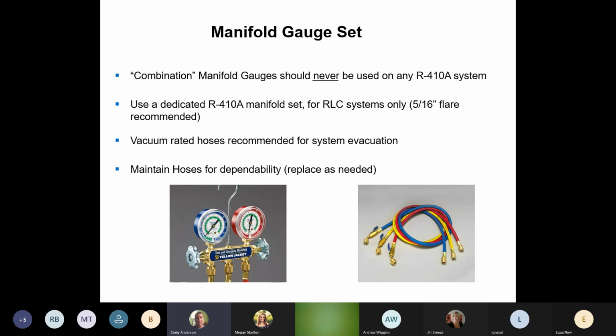Make sure your gauges are calibrated. Make sure your O-rings are good. They've been sitting for a while now, you haven't been using them. Get them out and take a look at them. There are O-ring kits to replace them, or just replace your hoses. Make sure everything's working fine. If your gauges aren't good, when you're doing a vacuum you could think that you have a leak in the system, when it's actually your gauges leaking and you're not pulling a proper vacuum. So make sure your gauges are good and well maintained.